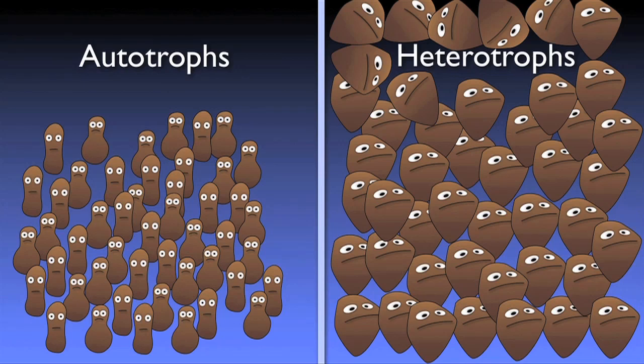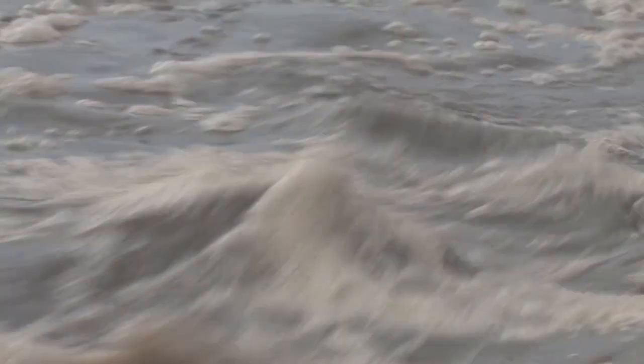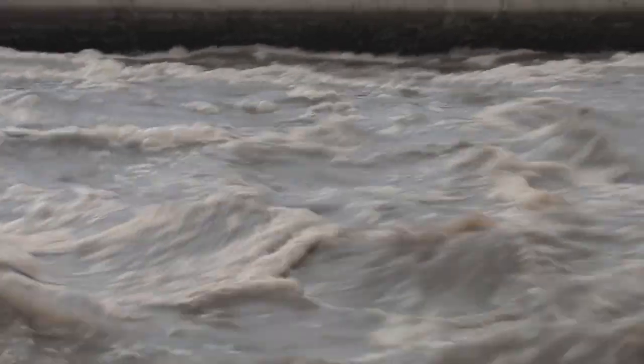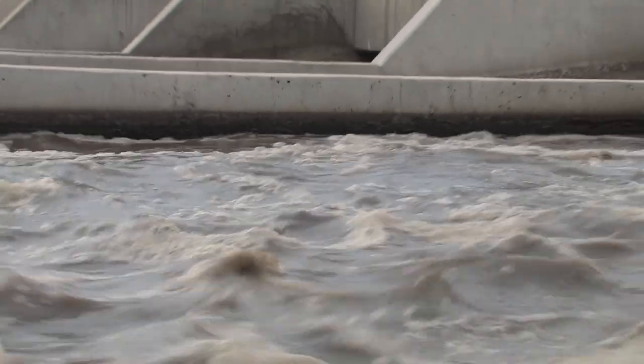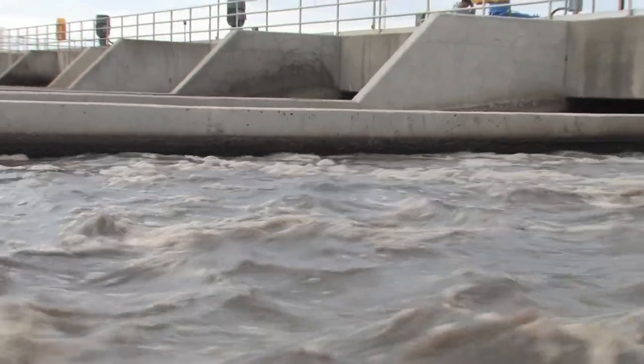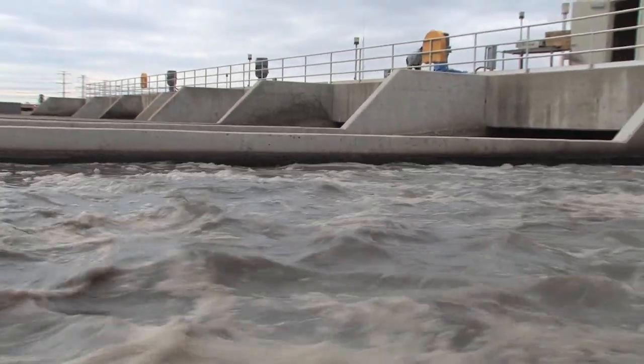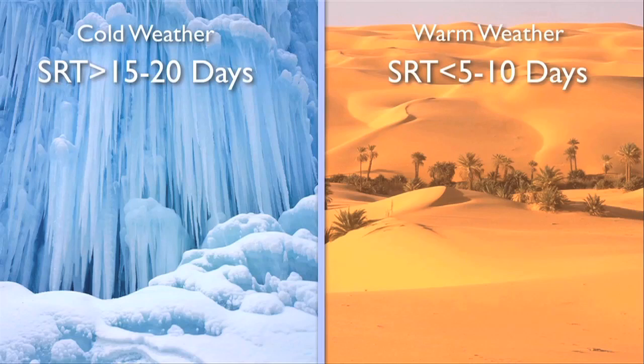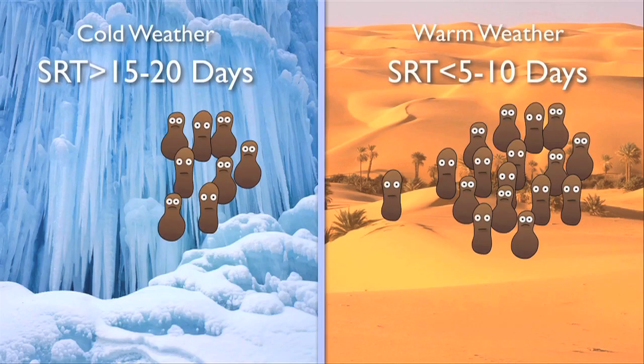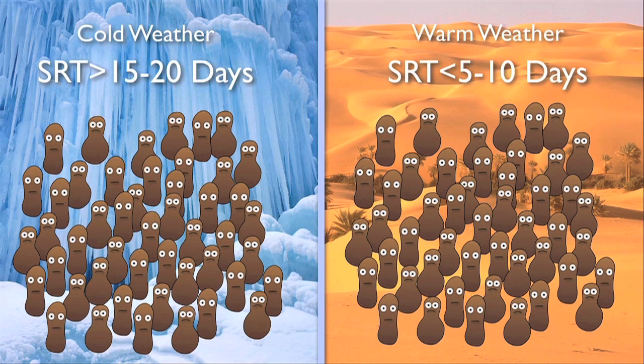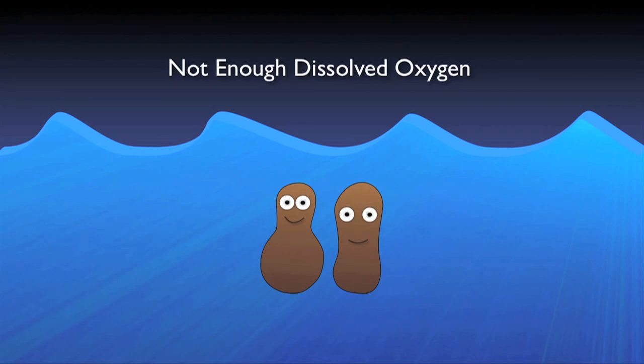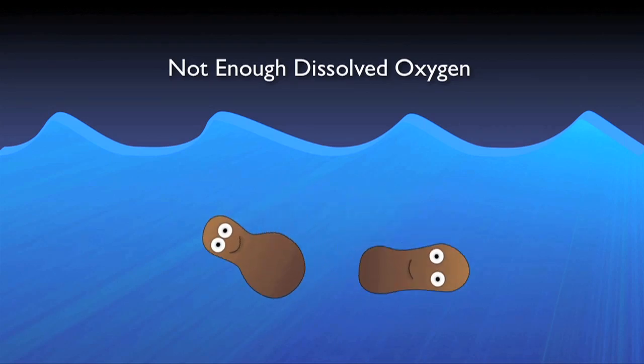The nitrifiers dictate the SRT in nitrogen-reducing plants. How fast nitrifiers grow depends on the temperature of the wastewater and the amount of dissolved oxygen present. If nitrifiers aren't allowed enough time to thrive, you run the risk of accidentally wasting them out of the system entirely and losing nitrification. Higher temperatures and DO concentrations mean faster growth; colder temperatures and lower DO concentrations mean slower growth. Also, when no DO is present, nitrifiers can become completely inactive.